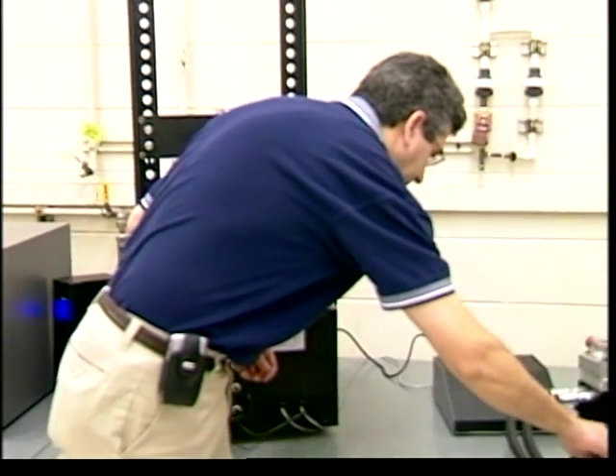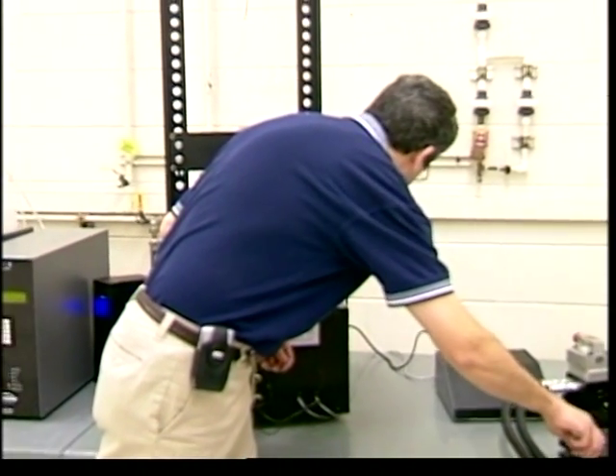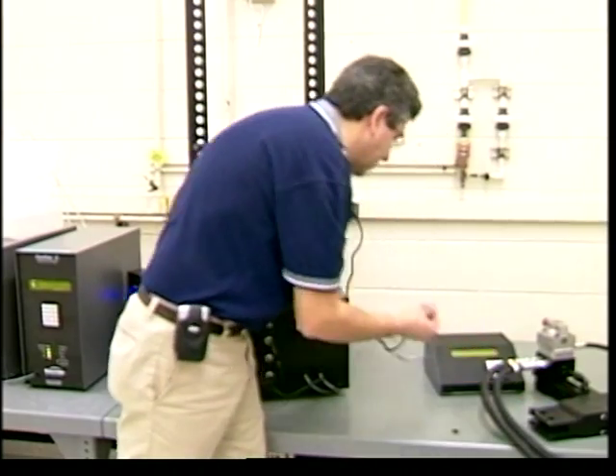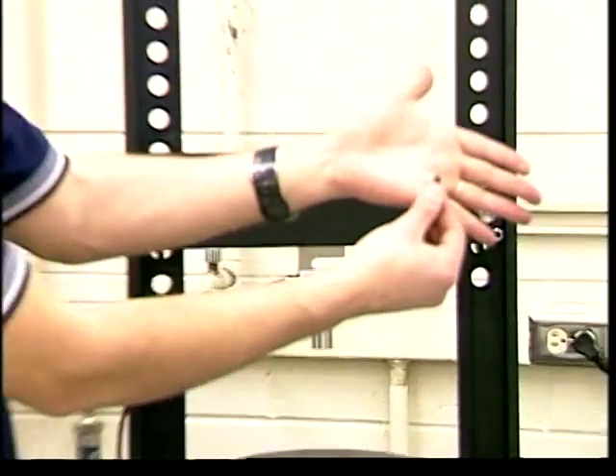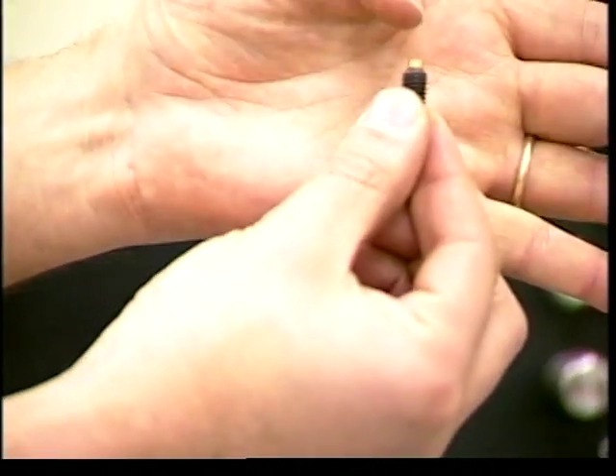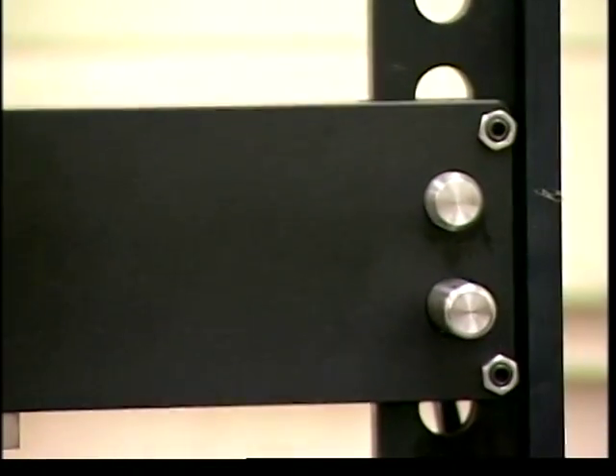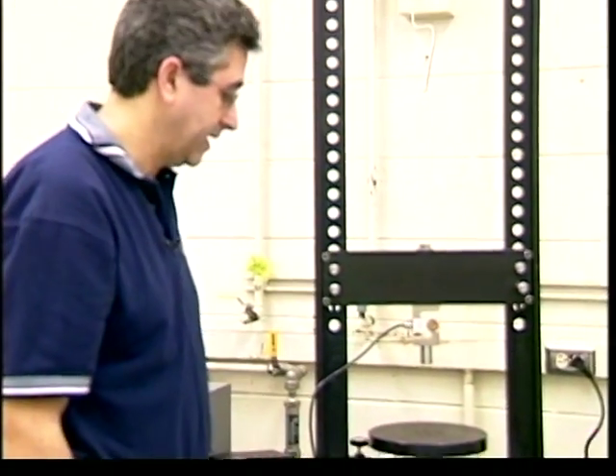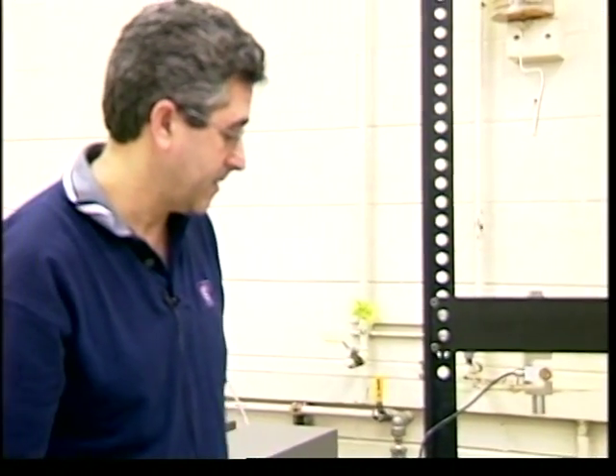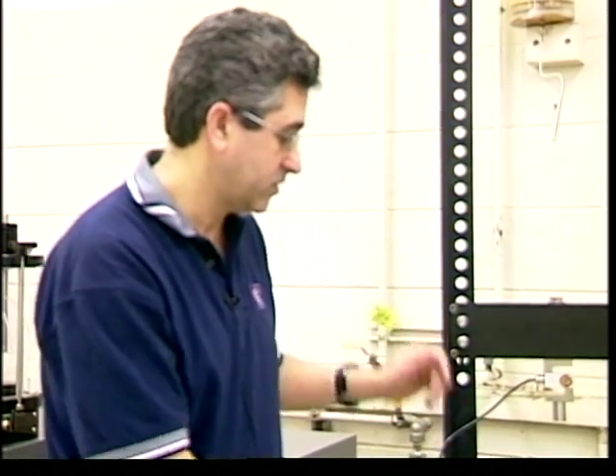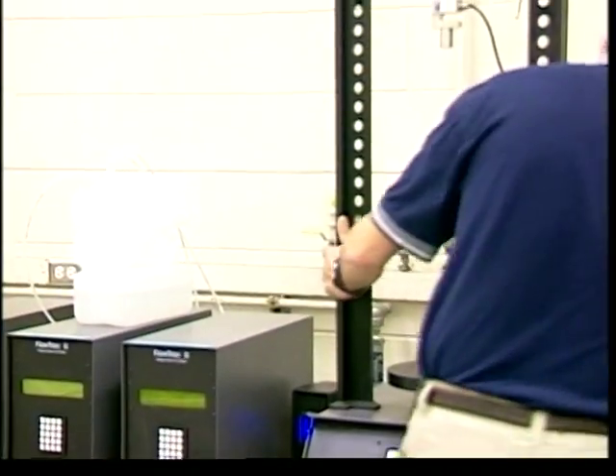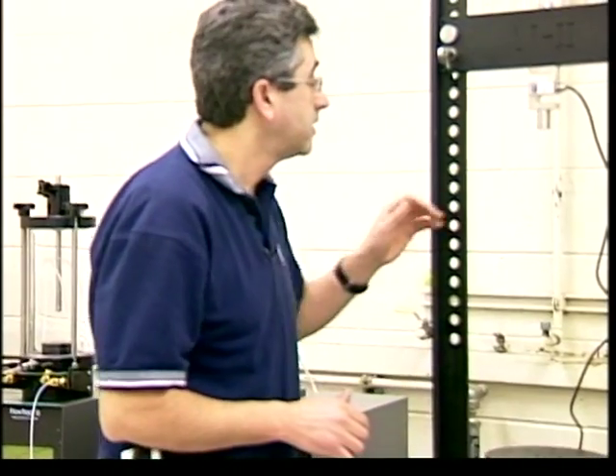The set screw is bronze tipped, so it does not scratch. This is your set screw here with a bronze tip on top. So there are 4 here. You can lock them permanently in place. And so that's, again, ready to go. There are very minimum connections here. So that's how the load cell is connected, and it should be registering here.